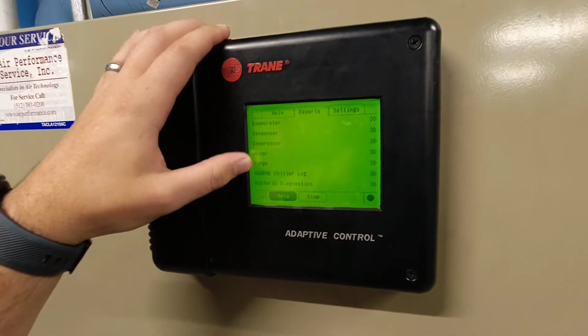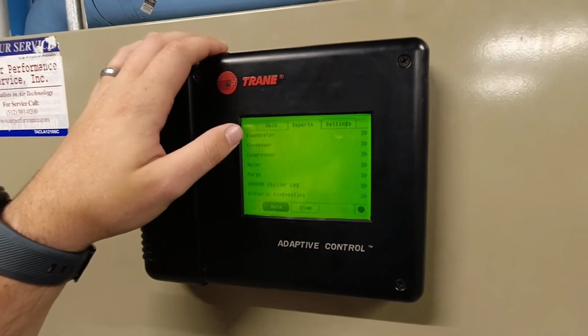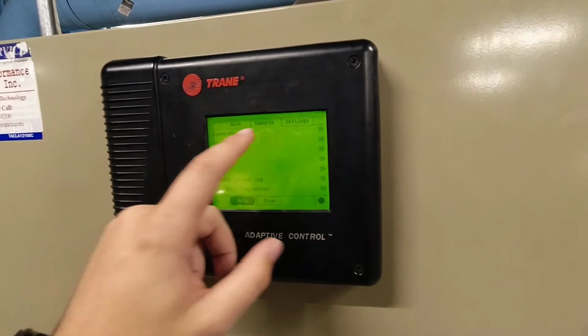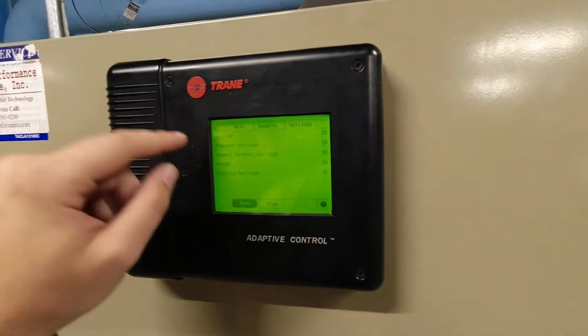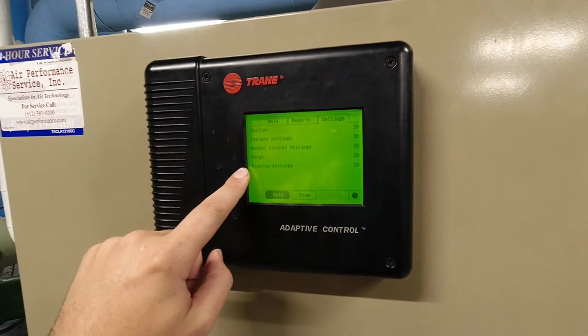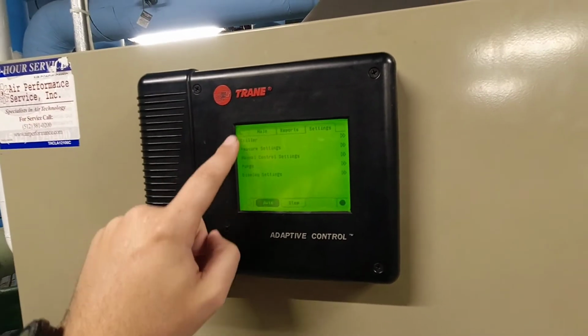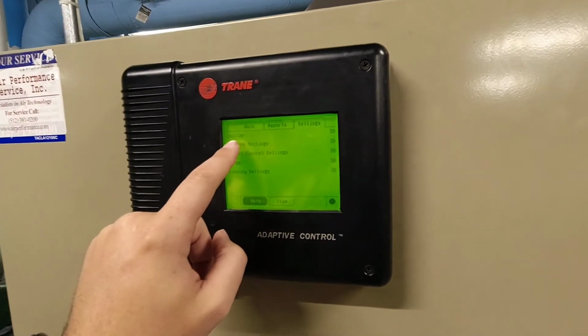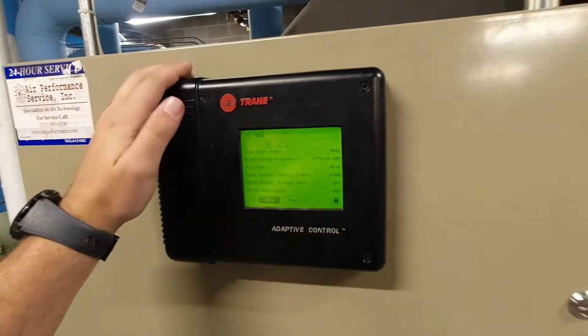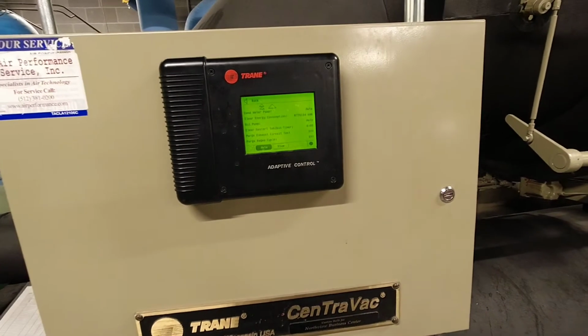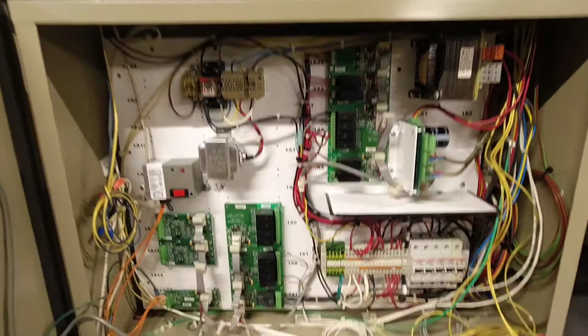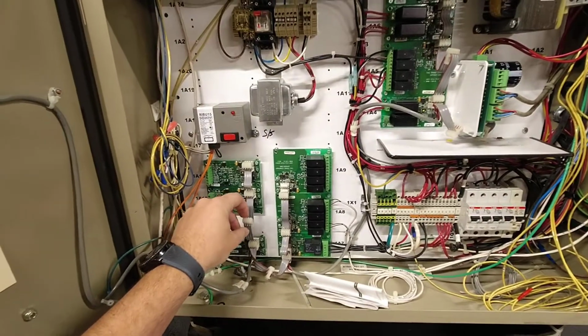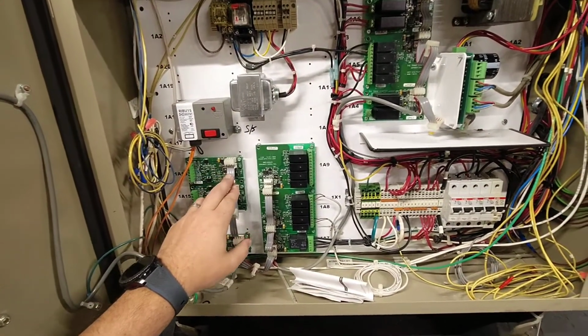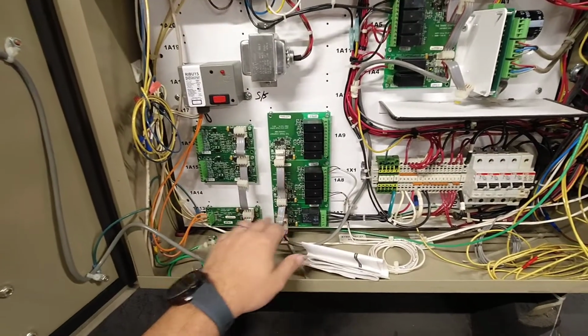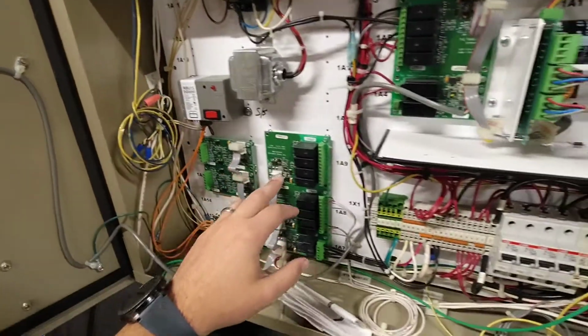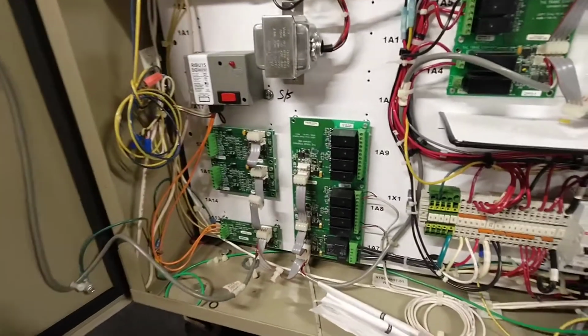In the meantime, this gives you all your different reports that the system is getting back. And then if you need to make changes to those reports, you could come over here to the settings and you can actually make the changes you need to: your manual control, turn your oil pump on, whatever you have that you want to do. From here you go into the main control panel. All of this on this particular series is done via a COM bus, and so all of these are little COM cards that all connect together and communicate back to the main controls.